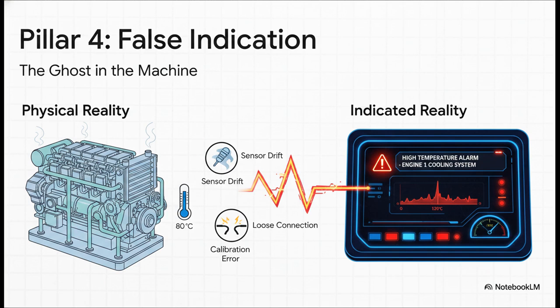And finally, we have Pillar 4, the ghost in the machine. Honestly, this can be the most frustrating one. The engine is fine, the cooling system is fine, but a sensor is telling you there's a problem. Maybe the sensor itself is drifting out of calibration. Maybe there's a loose wire in a junction box. Before you start pulling a system apart, you have to prove that the problem is even real.